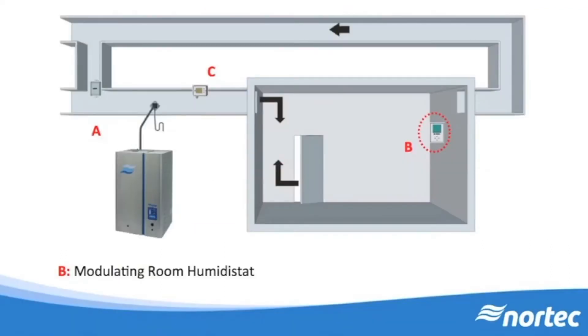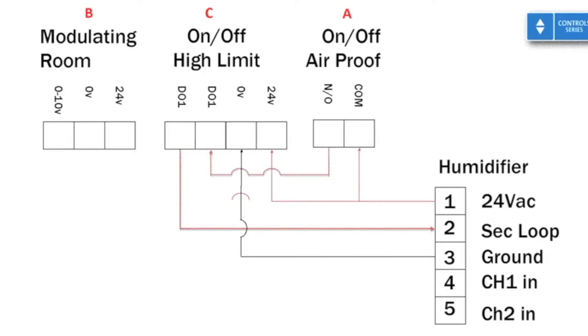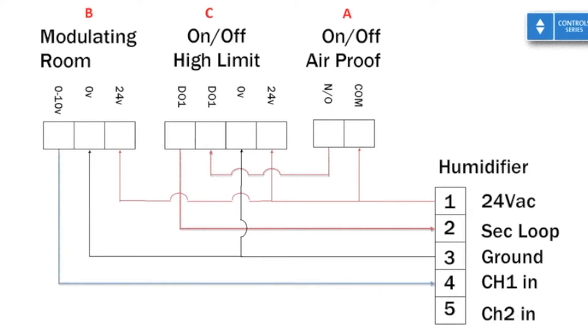Finally, the modulating room humidistat wires to the humidifier's modulating loop. These devices have internal circuitry and a visual display, so they need power to operate. We use 24 volts AC from the humidifier, pin 1, wired to the respective terminal on the humidistat, and ground, pin 3, to the respective ground pin. We then wire the modulating conductor, labeled 0 to 10 volts DC, to the humidifier's channel 1 modulation input, pin 4. Your wiring is now complete.